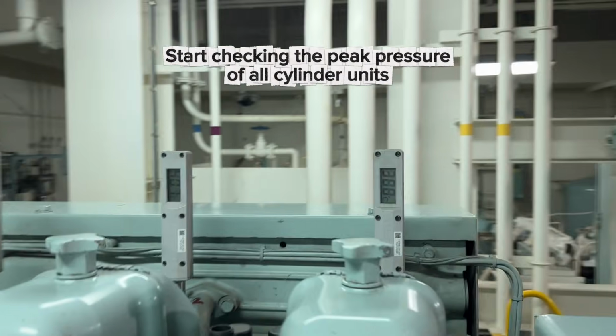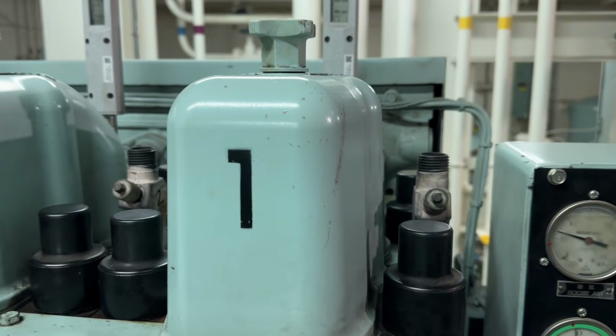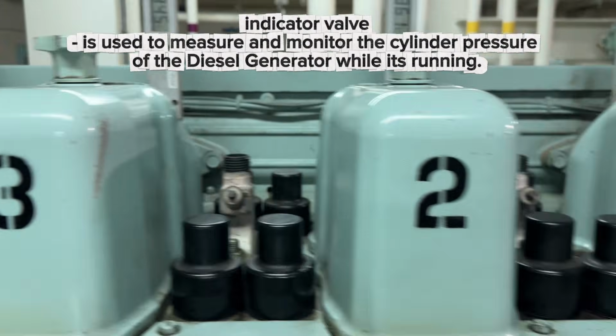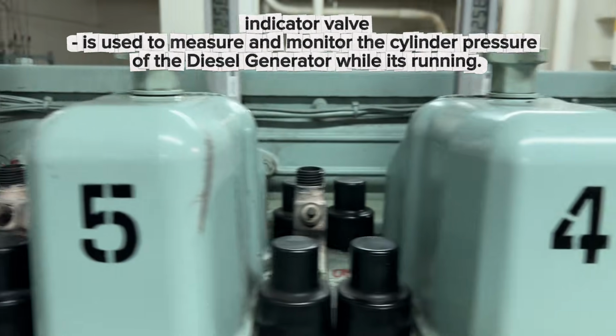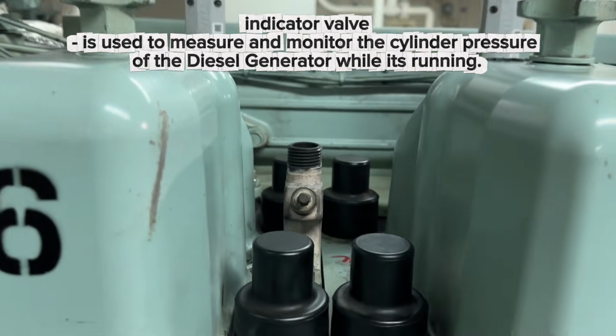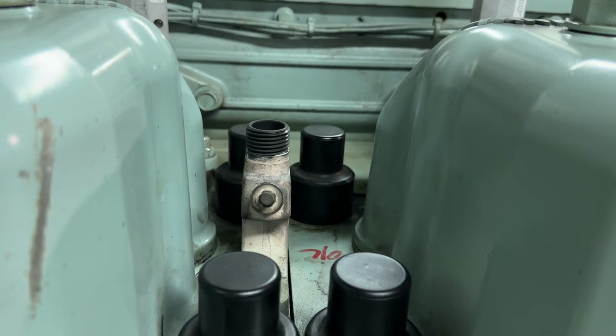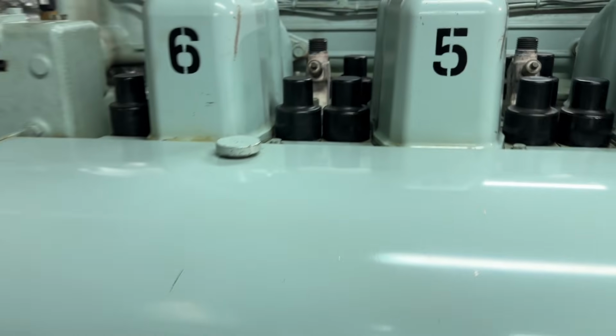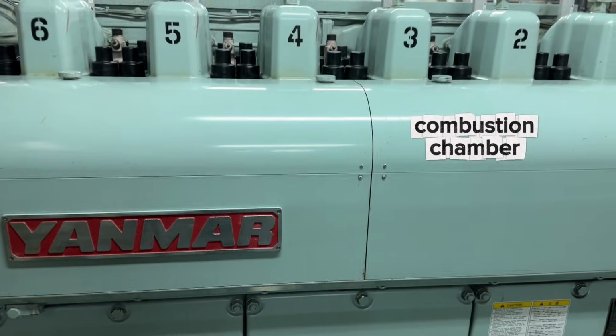Then, start checking the peak pressure of all cylinder units, starting from unit number 1. The indicator valve is used to measure and monitor the cylinder pressure of the diesel generator while it's running. This valve is mounted on the cylinder head and connects to the combustion chamber.